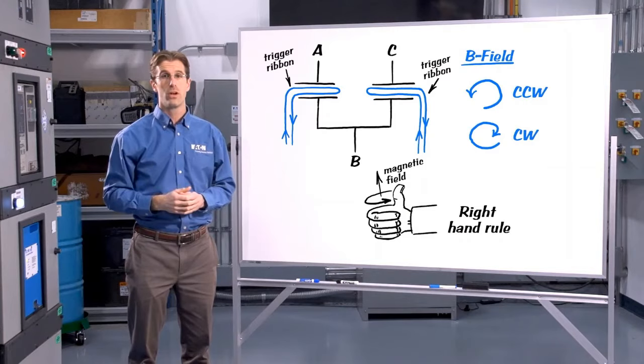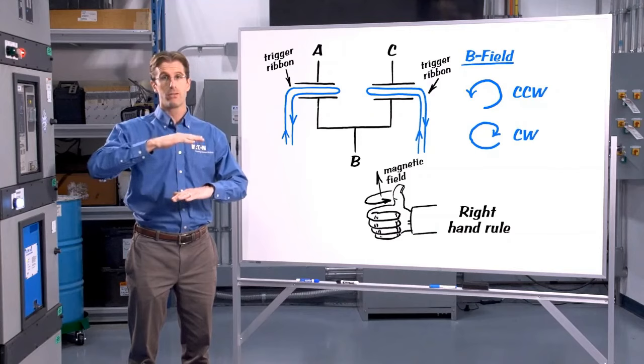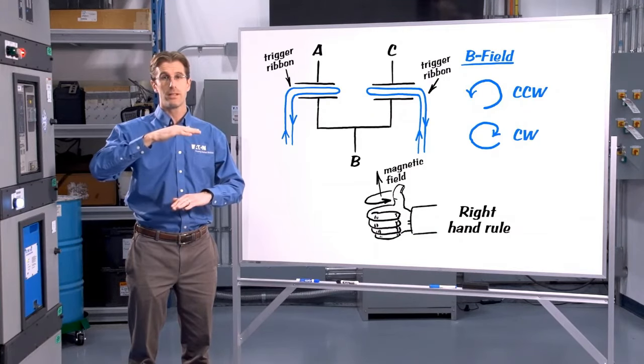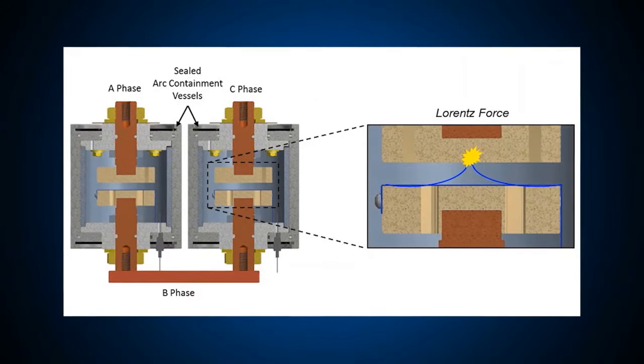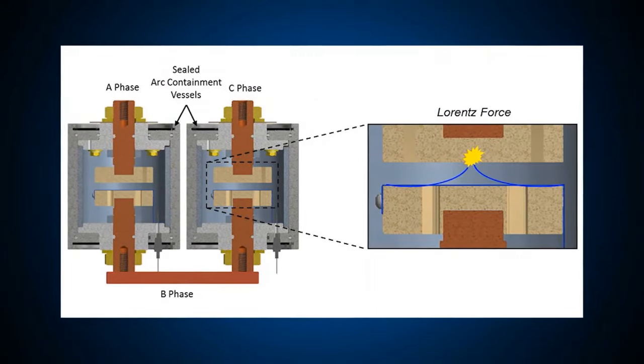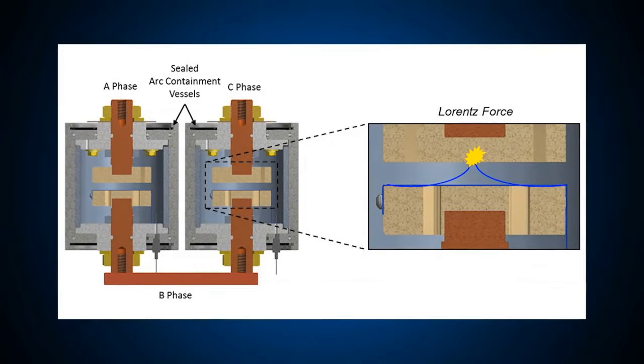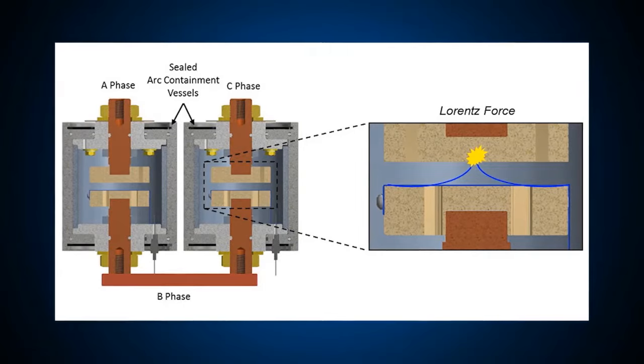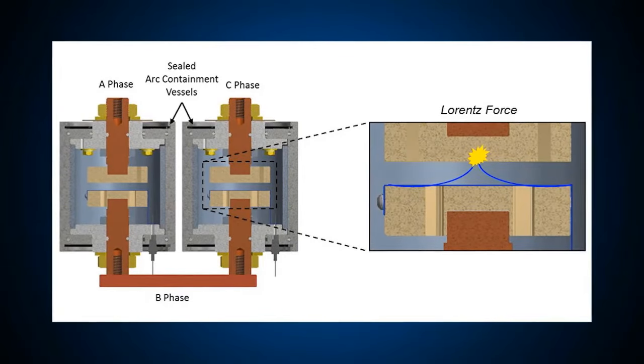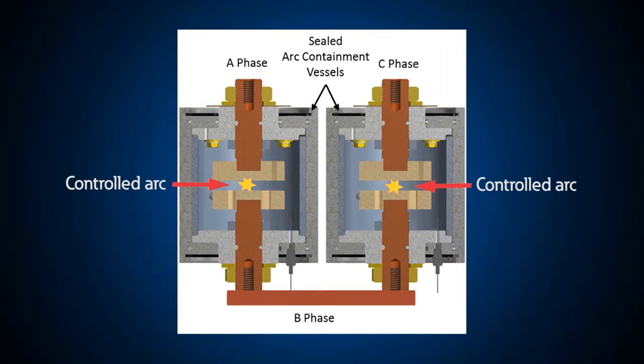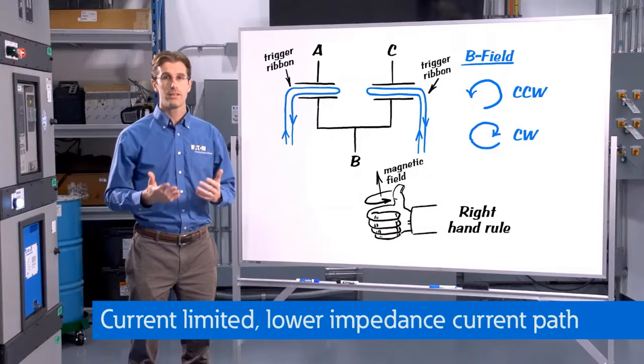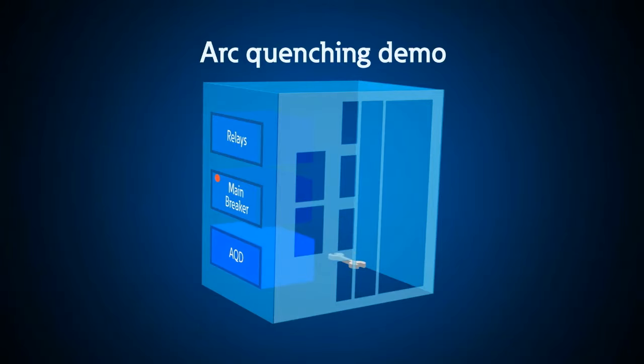In a matter of microseconds, we have created two opposing electromagnets in the wire. That causes the top half of the wire to be repelled from the bottom half, and it jumps up and hits the top contact. The trigger ribbons momentarily tie phase A to B and phase C to B. But the trigger ribbons are too thin to be able to conduct the available fault current and voltage, so the ribbons melt, they vaporize, and then they ionize. And when you ionize copper, you create an arcing fault. So we have spontaneously created two arcing faults that tie all three phases together. And that's how we create a current-limited, lower impedance current path, so that all the arcing energy flows into the arc quenching device and ceases to flow into the unintended arcing fault.